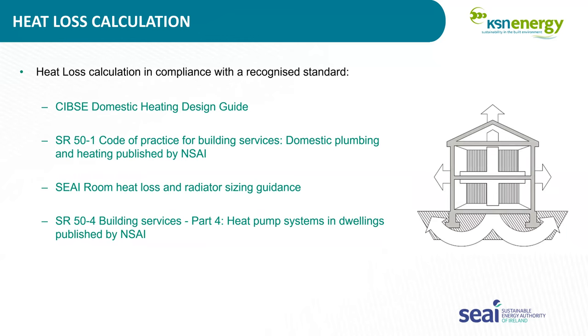Then, I suppose, the heat loss calculation. Historically, as Stephen said, I'm in this industry 25 years, probably more. When I started in the heating industry, we would have used a rule of thumb. We would have taken the length, breadth and width of a room, got the size of it in cubic feet and multiplied it by five. And that was what I would have used to size a radiator. That would have given me the amount in BTUs. And then I would have got a radiator conversion chart and looked it up and said, this radiator will give X amount of BTUs and it's suitable for the room. And that's how I would have picked that radiator.